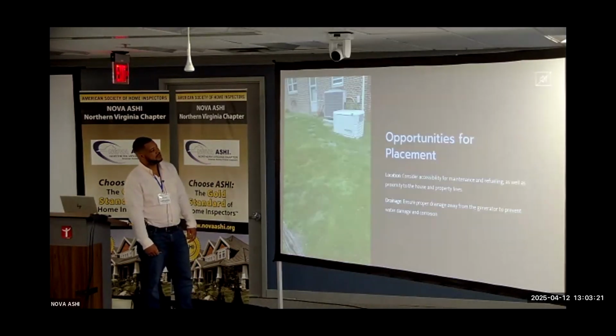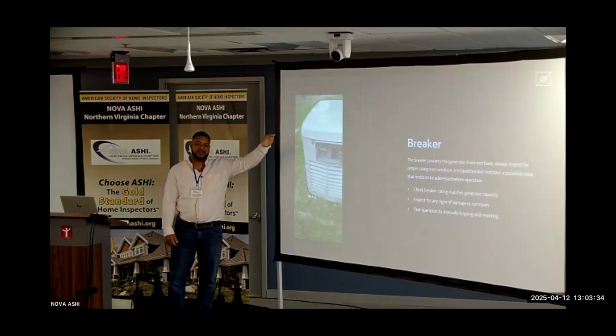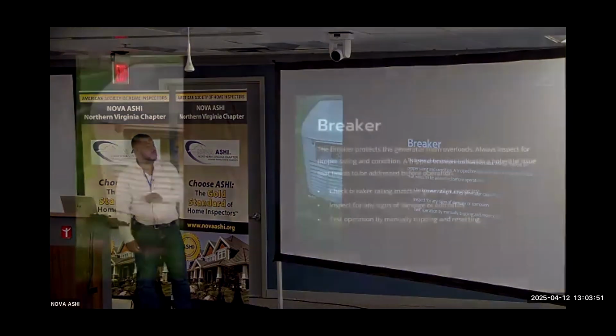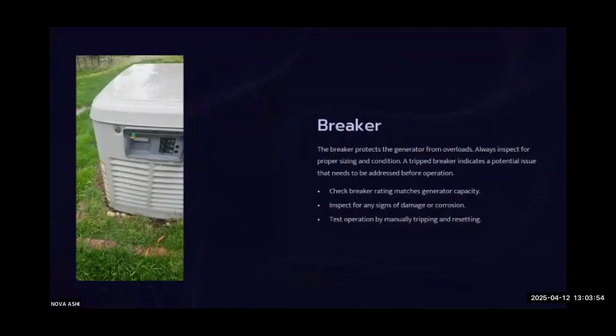So making sure that you have a stable service. Back to this one here, let's go here. The breaker — I believe the latest code now says that this breaker can actually be installed behind the lock of this unit to turn it off. Now you don't have to lock this door to be able to shut off the power. This breaker here is the generator power leaving the generator, feeding to the ATS and to the home. So if you ever want to kill the power going into the home, it's on the generator itself.